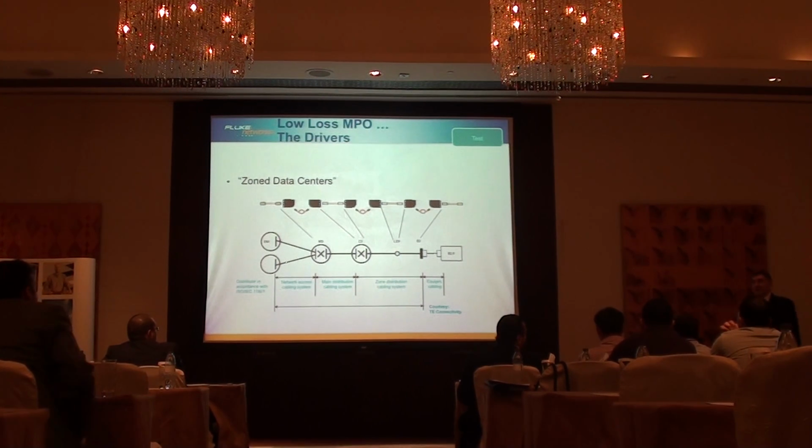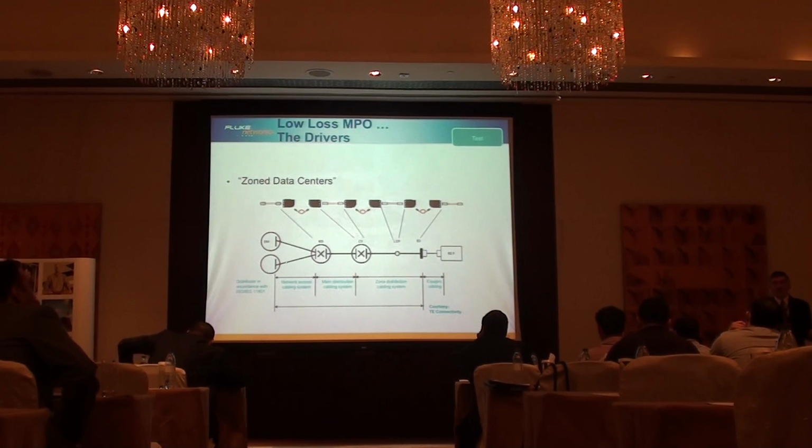I have to use the application standard. So you need to be educated on which standard you need to test against for which environment. Don't use a channel standard in a data center where you have MPOs. You're going to get unrealistic results. Okay?